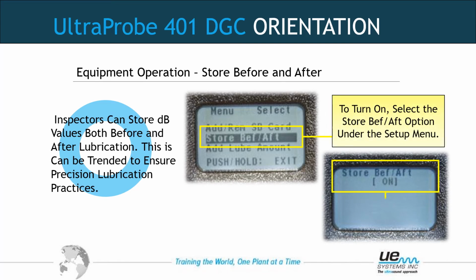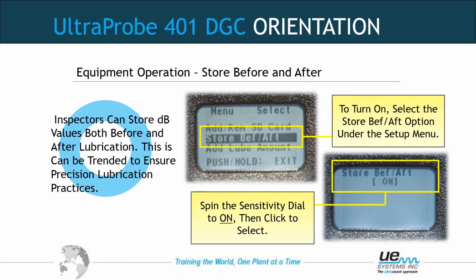The second option, and you can see the Add Remove SD card option is number 1 item that pops up into the menu. If you'll rotate, once you're into the menu area, if you rotate the sensitivity dial to the right, we'll start highlighting as we go down and talk about these. Here we have store before and after. Inspectors can store a decibel value both before and after the lubrication if this item is turned on. This can be trended to ensure precision lubrication practices. So once we download, you'll have 2 readings in the DMS software, one right before lubrication and one right after lubrication. And hopefully all went well and you'll see a lower decibel in that second reading.